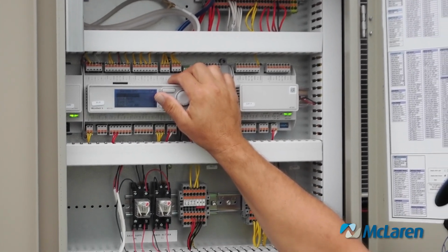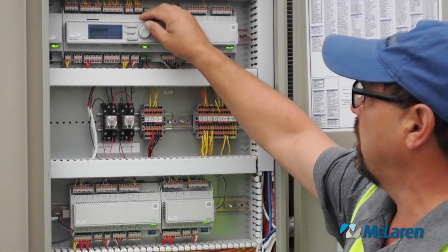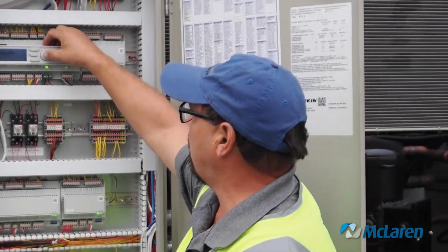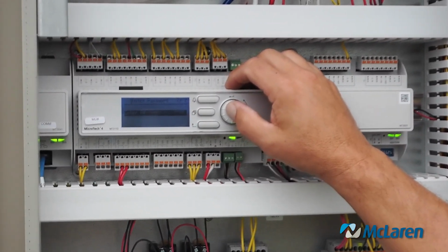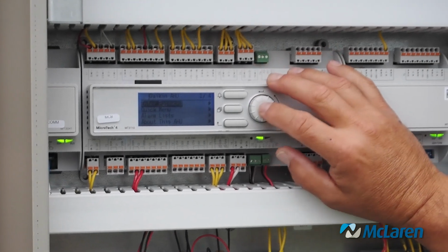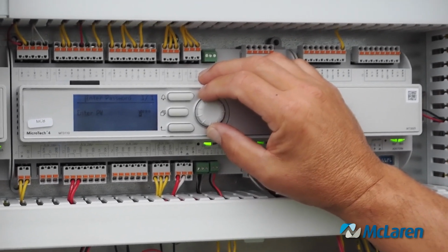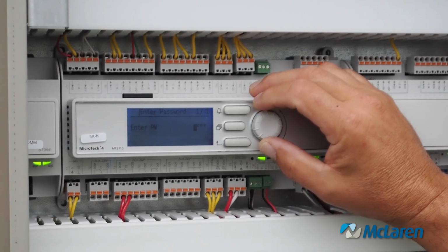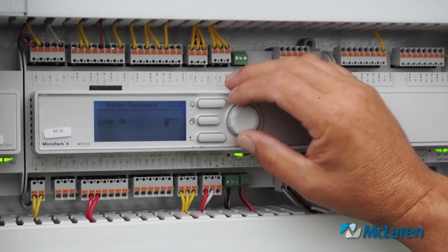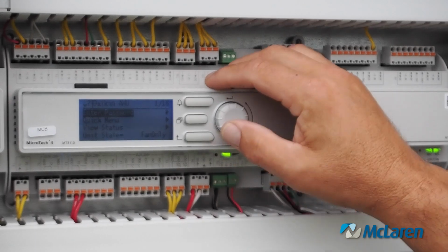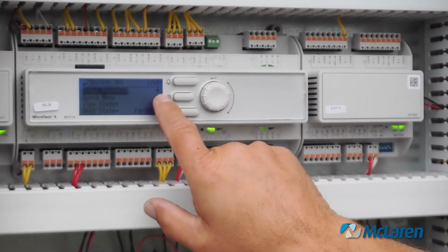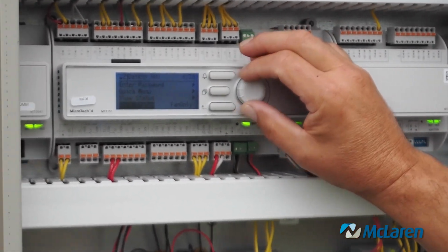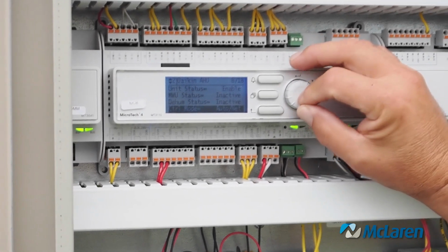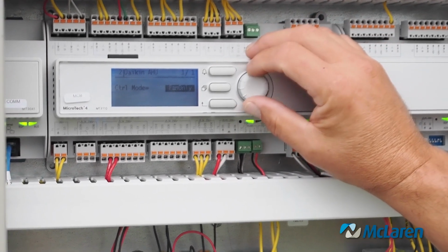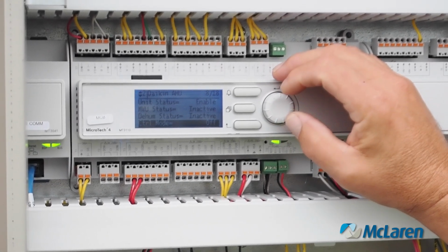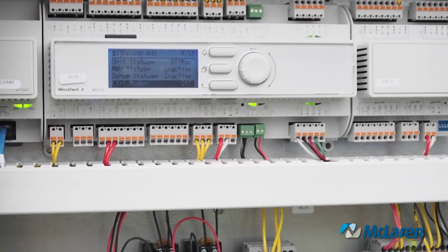So we're only going to kill control voltage, we're not going to kill main power voltage. To do that, you're going to have to enter a password. Password is 6363. You do that by hitting the enter button, turning the dial, enter twice, turn the dial till you get to the 4-digit section and you enter 6363. Now you know you did that right because you have 18 items instead of 4. You will scroll down to control mode, enter, and then scroll to off. Now the unit is doing a quiet shutdown.